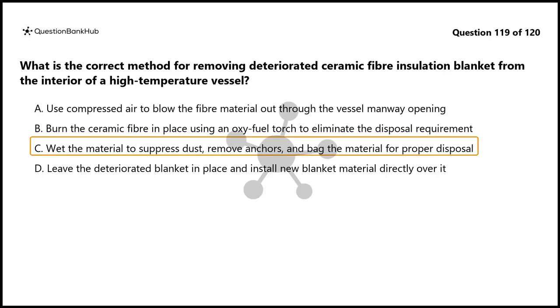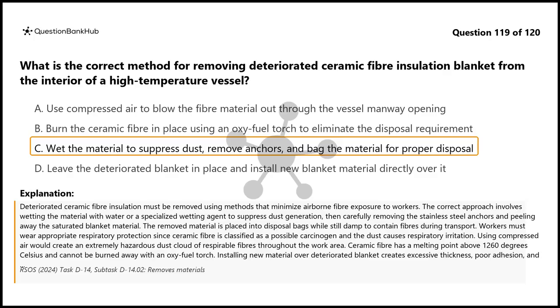The correct answer is C. Deteriorated ceramic fiber insulation must be removed using methods that minimize airborne fiber exposure to workers. The correct approach involves wetting the material with water or a specialized wetting agent to suppress dust generation, then carefully removing the stainless steel anchors and peeling away the saturated blanket material. The removed material is placed into disposal bags while still damp to contain fibers during transport. Workers must wear appropriate respiratory protection since ceramic fiber is classified as a possible carcinogen and the dust causes respiratory irritation. Using compressed air would create an extremely hazardous dust cloud of respirable fibers throughout the work area.